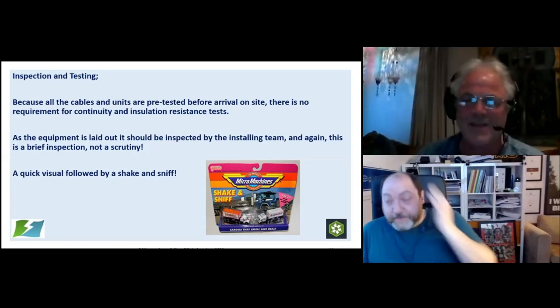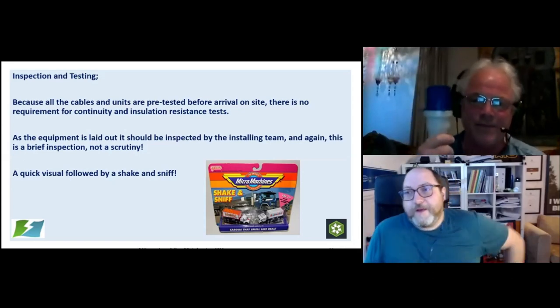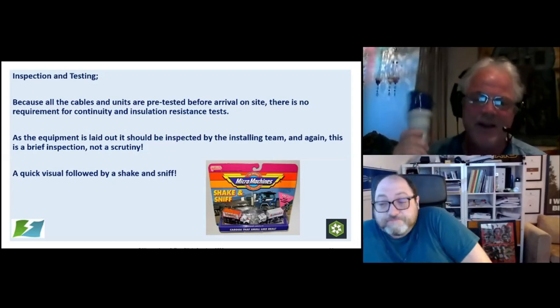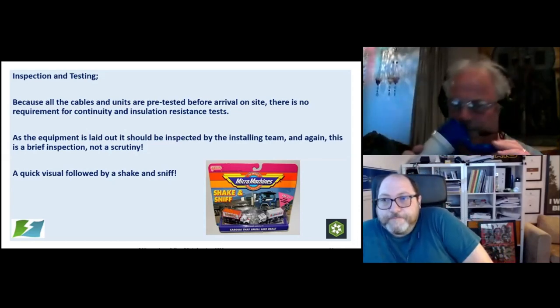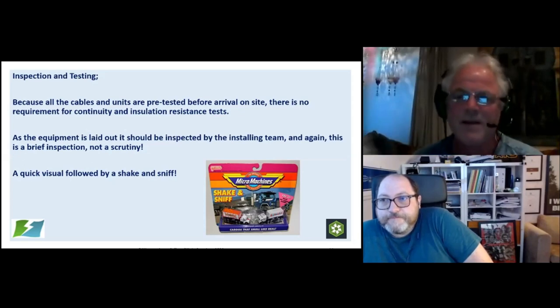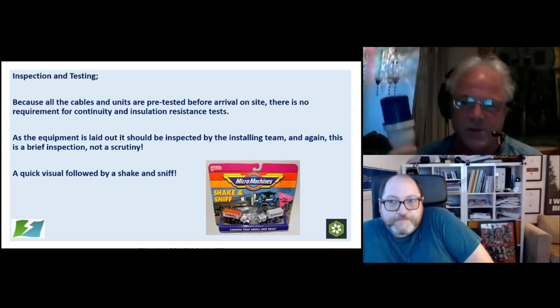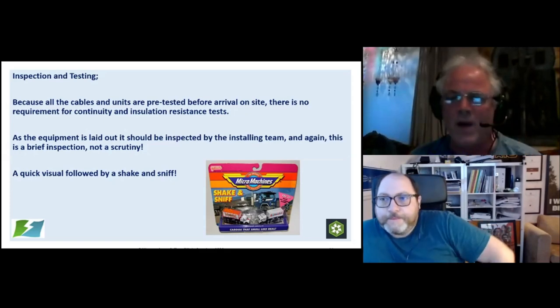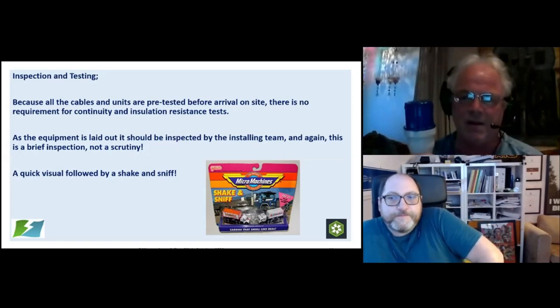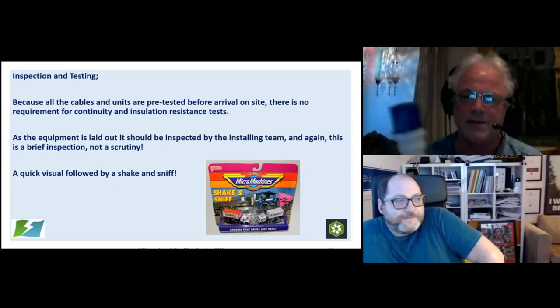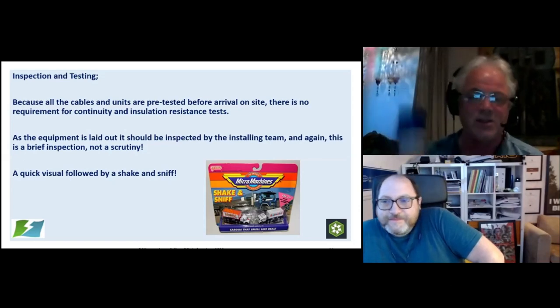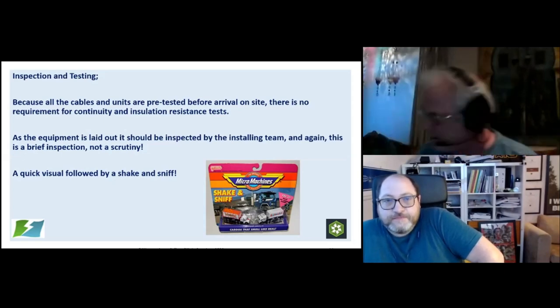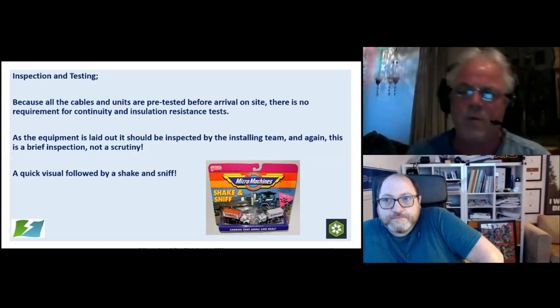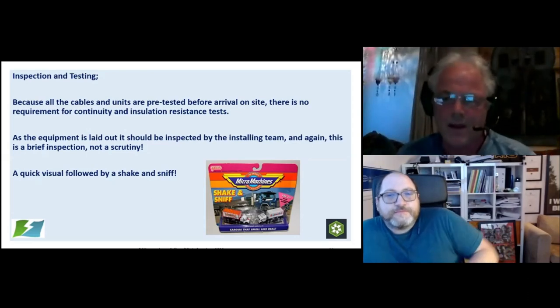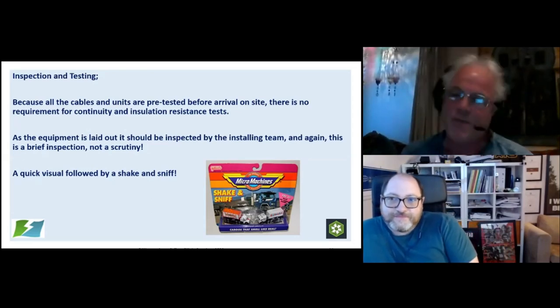What is shake and sniff? So shake and sniff. So you've got the coupler. Yeah. Give it a shake. If you hear it rattle, there's a screw loose. Yeah. Give it a sniff. If it smells funny, okay, you know that there's a bit of arcing or loose connection inside. You'll smell it way before you see it, and way before it sort of starts to catch fire. So that simple action as you're laying out the lead, shake it, sniff it. Takes a couple of seconds, okay? It's so important, and it can detect issues that may have been missed.